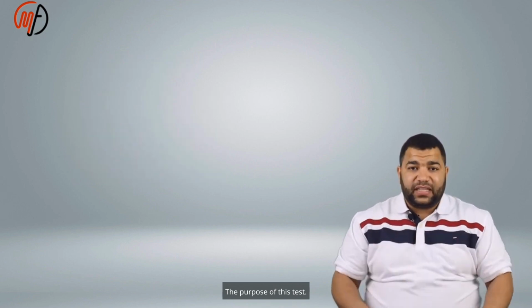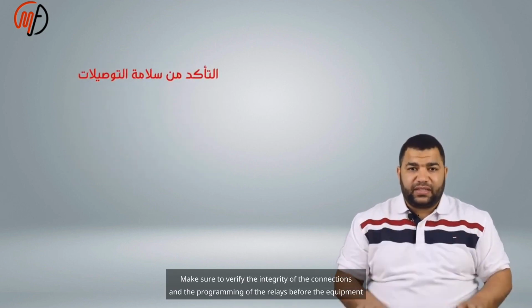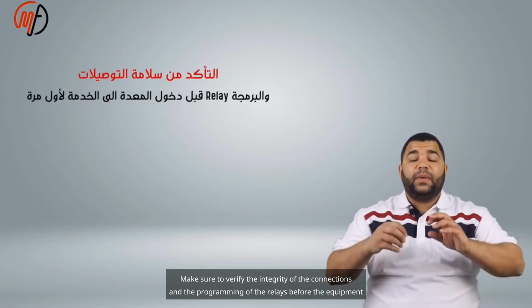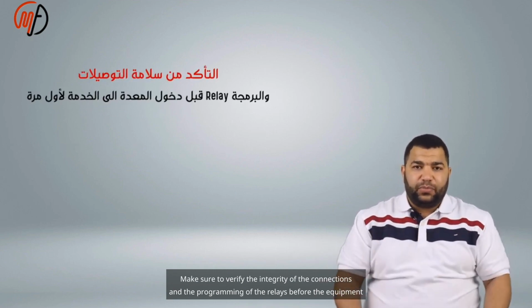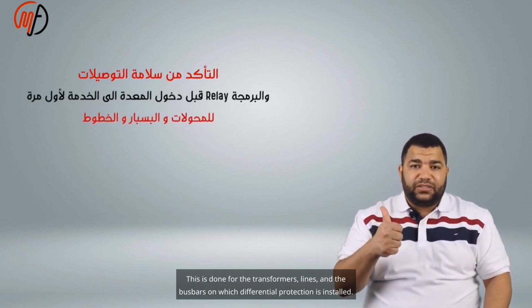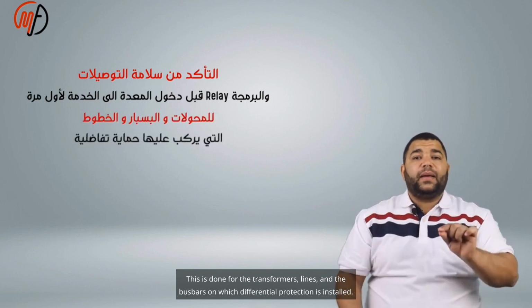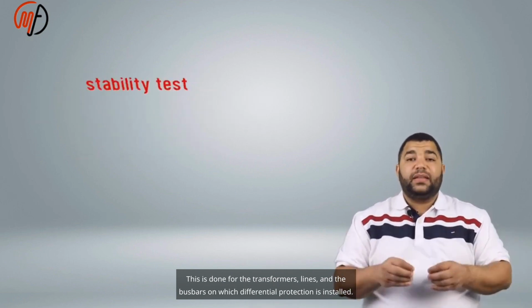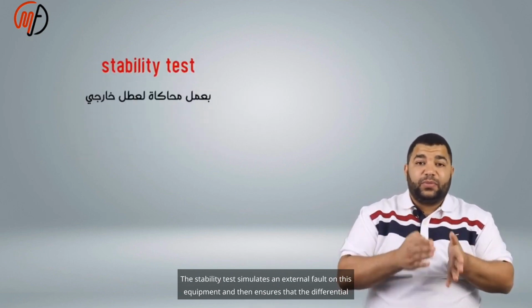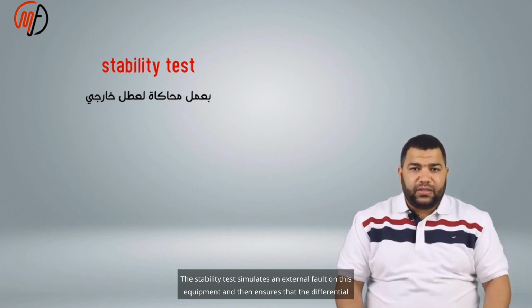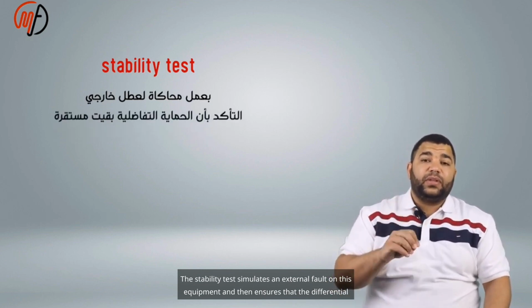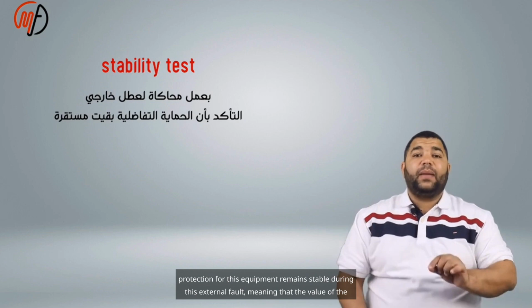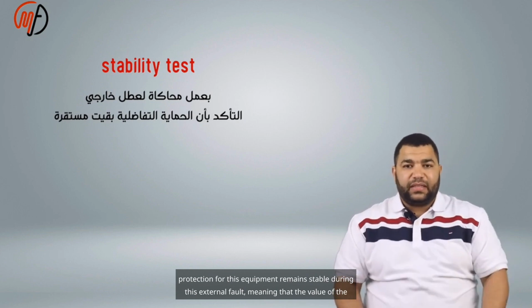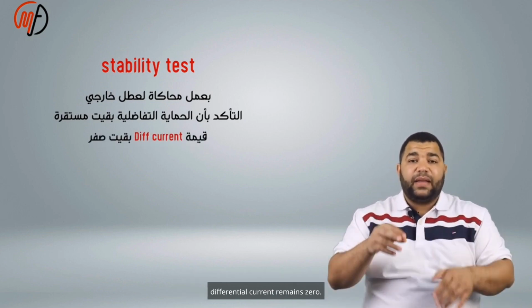The purpose of this test is to verify the integrity of the connections and the programming of the relays before the equipment is put into service for the first time. This is done for the transformers, lines, and the bus bars on which differential protection is installed. The stability test simulates an external fault on this equipment and then ensures that the differential protection remains stable during this external fault, meaning that the value of the differential current remains 0.